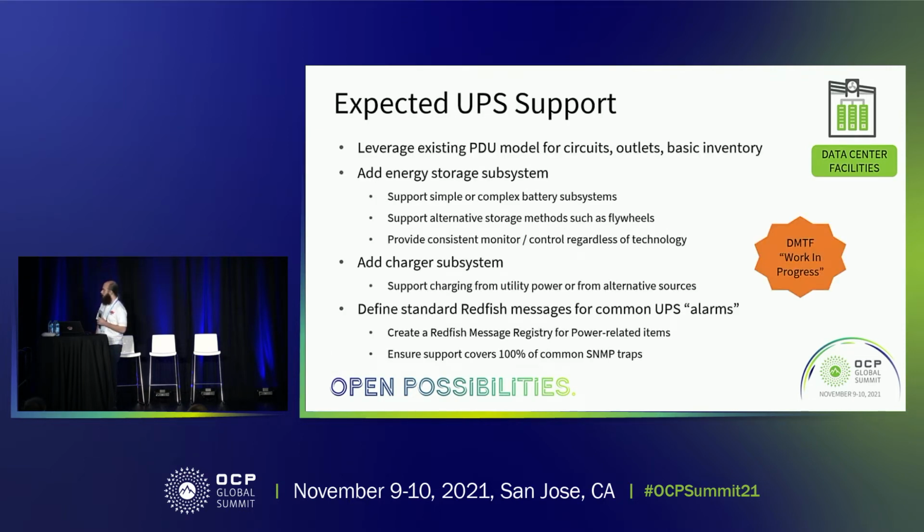So at least looking more at what we're proposing for UPS modeling, what we really want to do is extend the existing model that we put in for PDUs, since they are rack-mounted power devices. Maybe they're large and they don't fit inside of a rack, but they're still a piece of power equipment with outlets, circuits, and other types of power monitoring. So the additions we need to consider for this is creating what we're proposing as an energy storage subsystem. So how is energy stored in your UPS? Is it batteries? Is it flywheels? Is it supercapacitors? Could be anything.